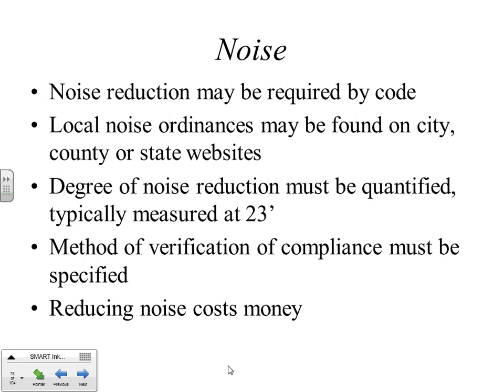The reduction may be required by code, usually is. And the ordinances can be found a lot of times right on the city's websites or county, whatever municipality we're looking at. The degree of noise reduction must be quantified, typically measured at 23 feet. Why they pick that distance, I don't know, but 7 meters or 23 feet is how generator manufacturers usually define their quantitative noise. And engineers need to specify the method of verification of compliance. And reducing noise does cost money, in fact, a lot of money.